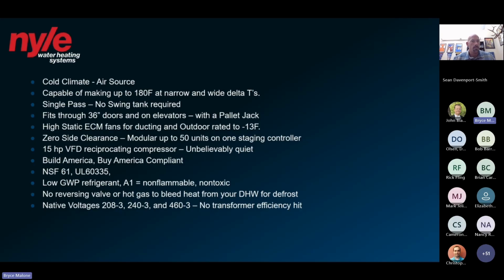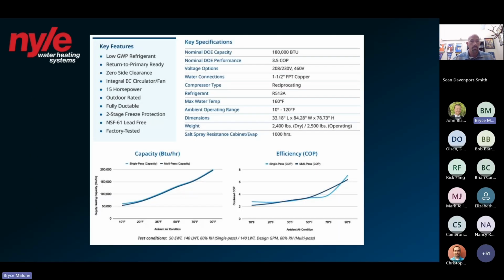There is no reversing valve, so you're not going to have to worry about your domestic hot water affecting your defrost, because we use a specific type of defrost with electric resistive elements embedded into our evaporator coils, which allows us to do defrost relatively quickly, within 4 to 6 minutes, versus a reversing valve or hot gas bypass, which can take hours. And while you're in that mode, you're actually not making domestic hot water, so you would be specifically on resistive or some sort of backup during the time of defrost. These are available in 208, 240, and 460, and it will not have any sort of efficiency hit on the transformer.